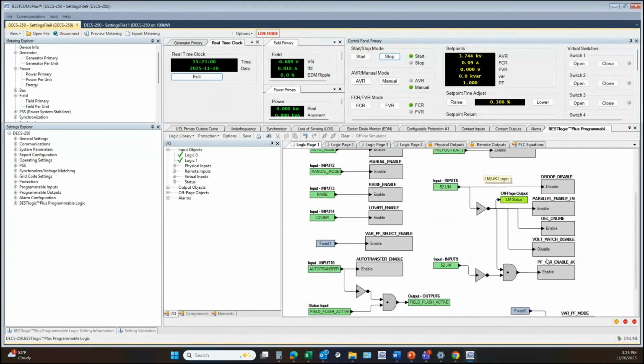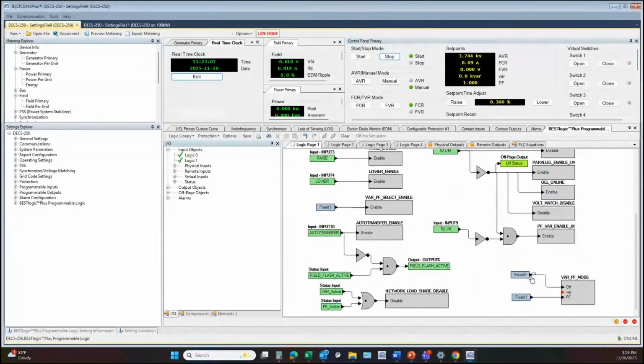So again, I scroll down, find where it's at, and then reconnect that. My indicators are green. And then above the logic pages, there's a save bar, or this bar that has some icons, and to the left of those icons is a save option. It's not saving it to the unit, it's not saving it to your computer, it's just saving the logic scheme as part of your open file. So now all my indicators are green. Once I have all 3 of those green, then my unit can accept it.